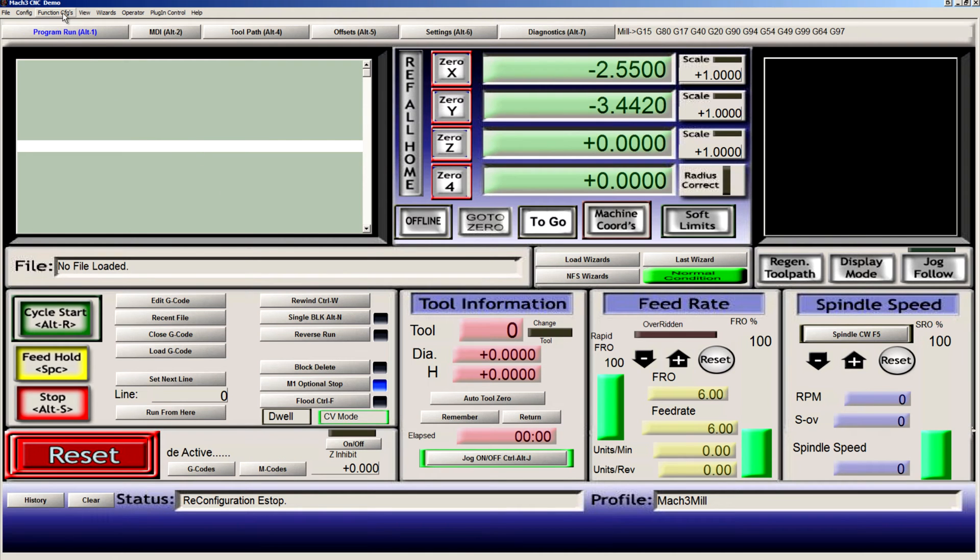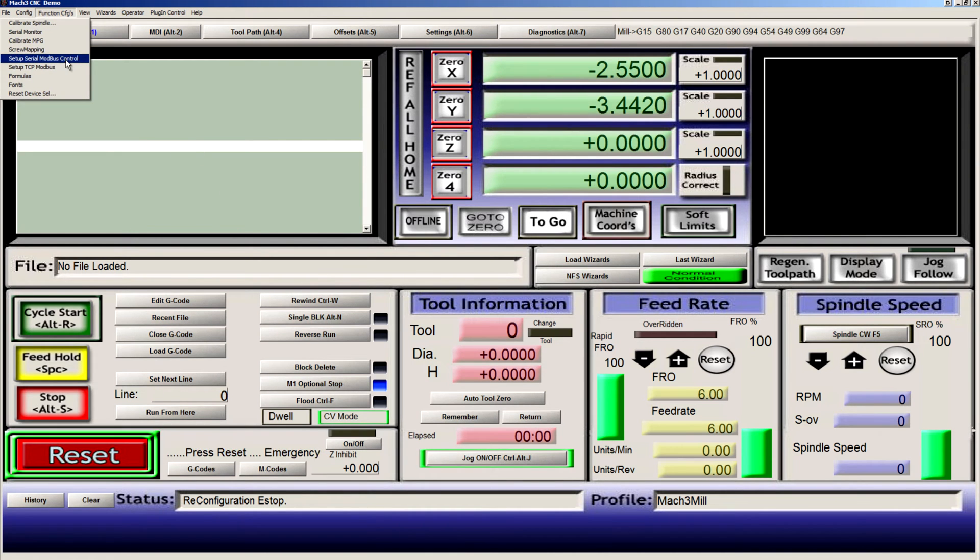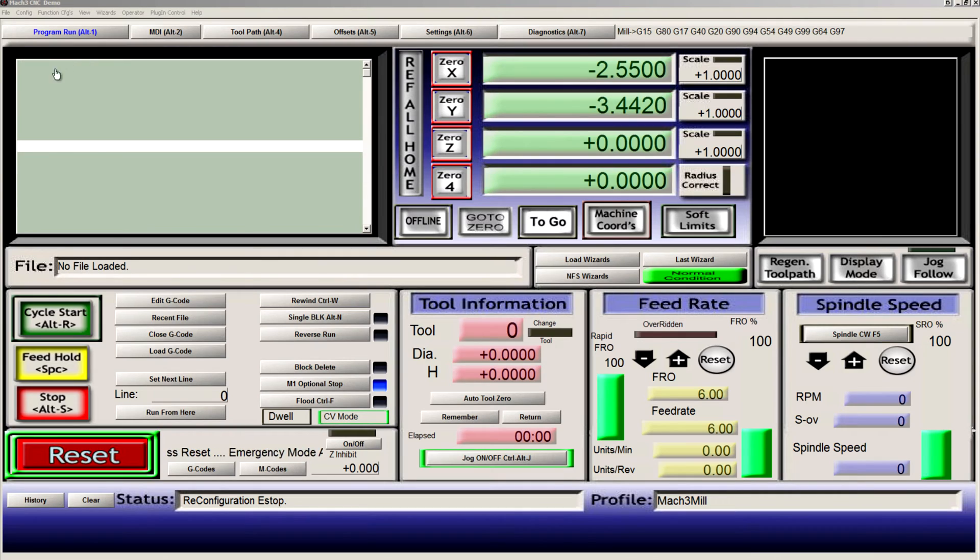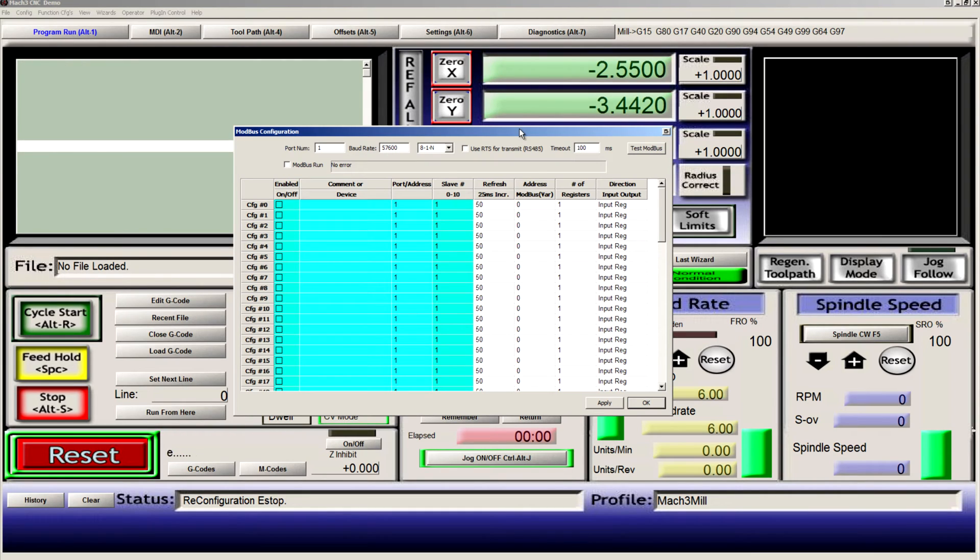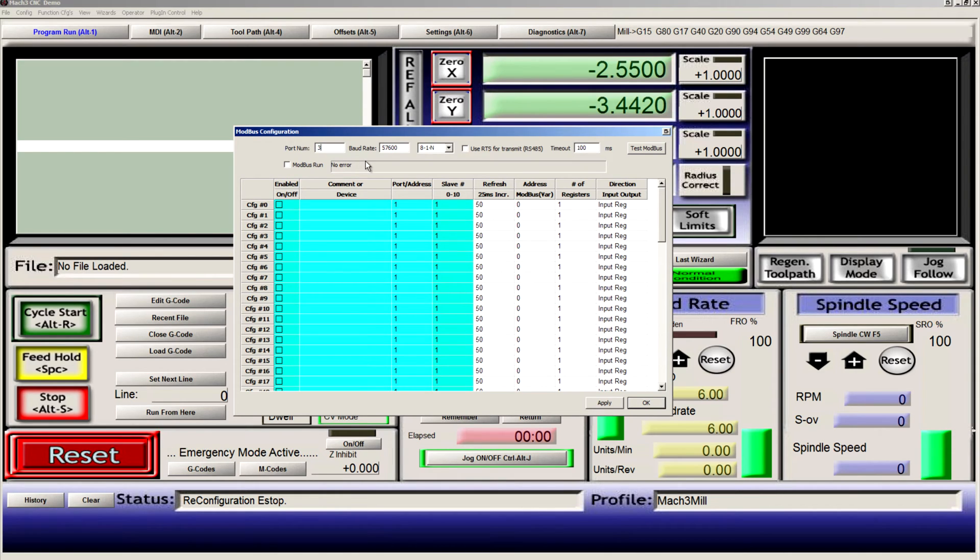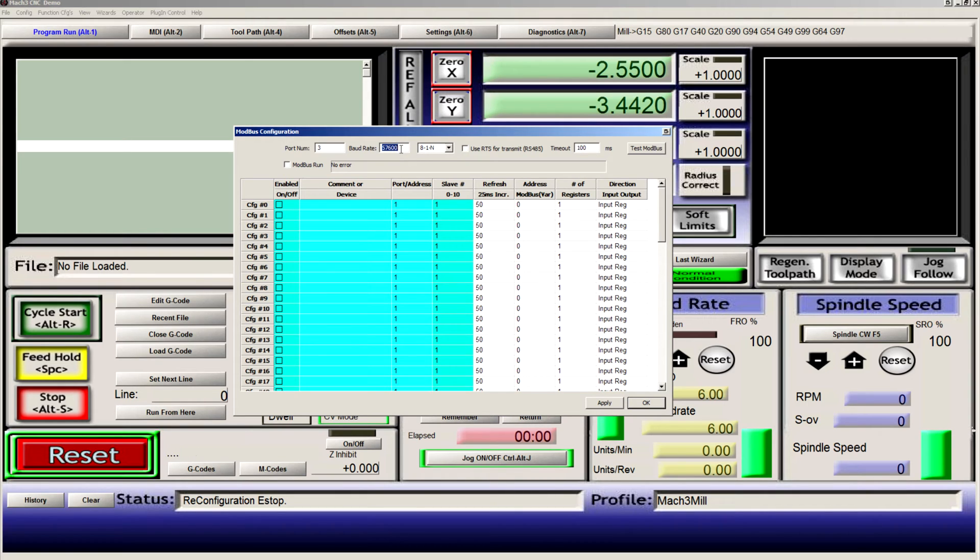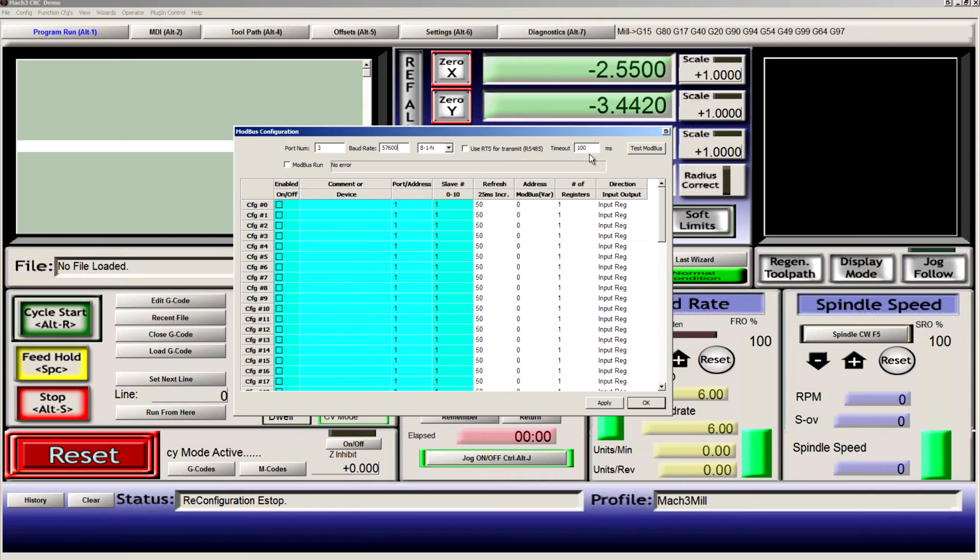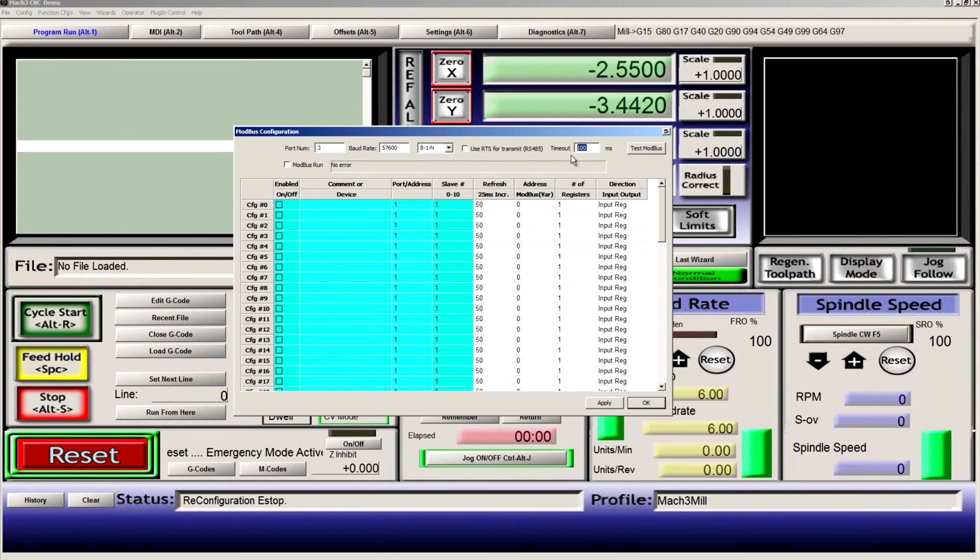Now we can go to function configs, set up serial Modbus control, and if you have the plugin successfully enabled, you'll see this screen. Set the serial port number that our adapter is on, serial port 3 for me. The baud rate, make sure that this is the same that we set the VFD to, and make sure that you have the timeout set above 30 milliseconds.